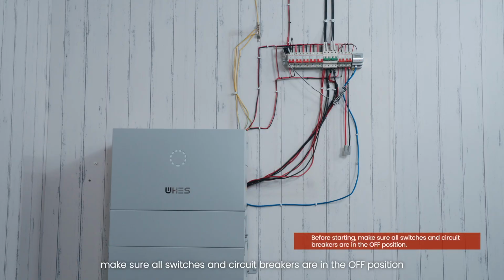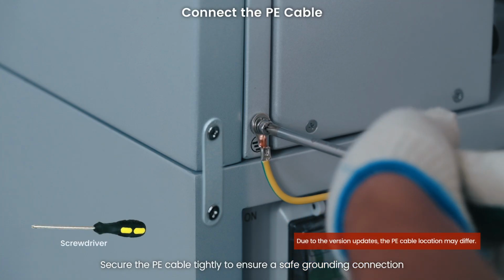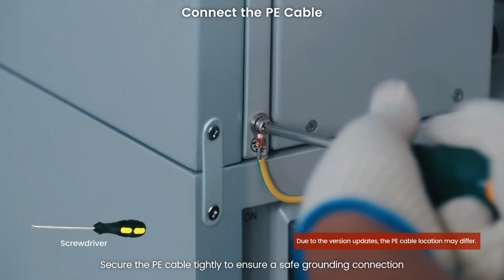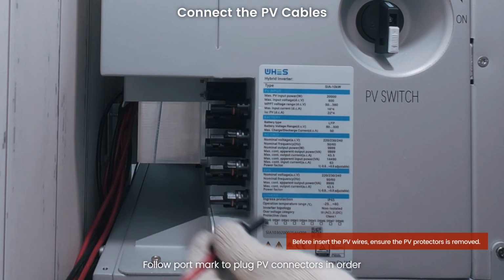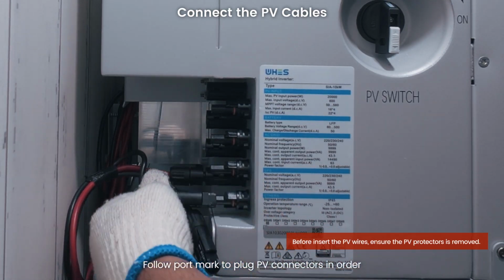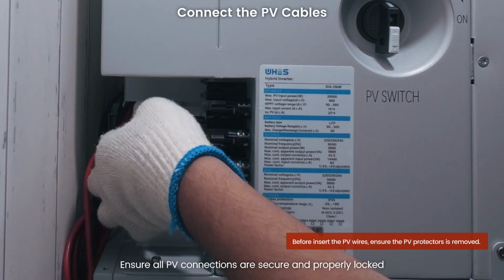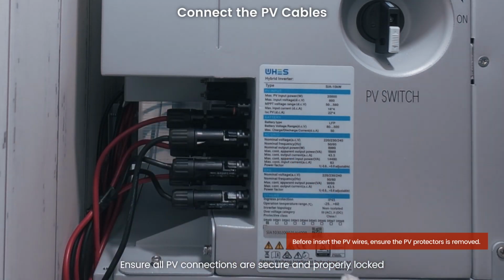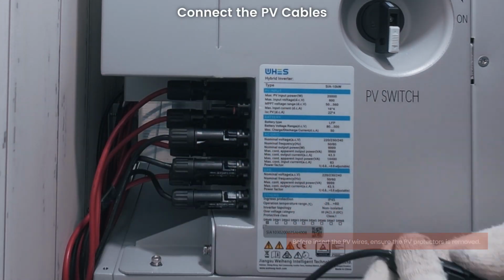Before starting, make sure all switches and circuit breakers are in the off position. Secure the PE cable tightly to ensure a safe grounding connection. Follow the mark to plug PV connectors in order. Ensure all PV connections are secure and properly locked.